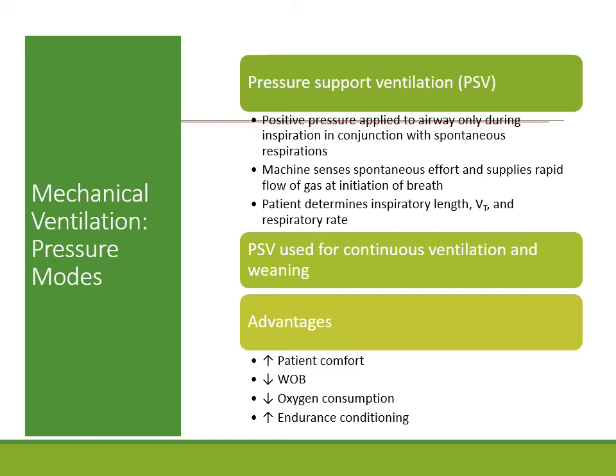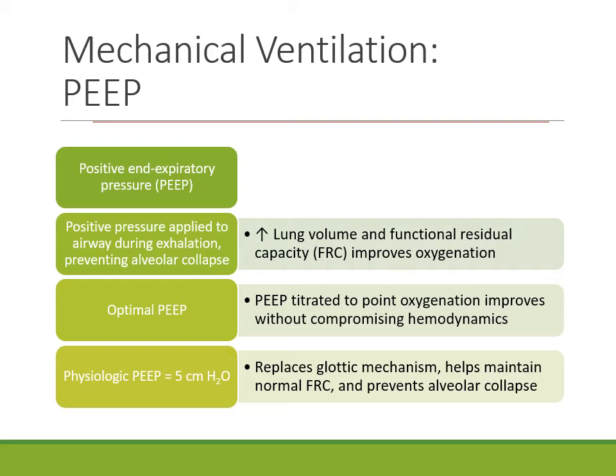With PSV, the patient determines the inspiratory length, tidal volume, and respiratory rate. Tidal volume depends on the pressure level and the airway compliance. Positive end-expiratory pressure, or PEEP, is a ventilator maneuver in which positive pressure is applied to the airway during exhalation.